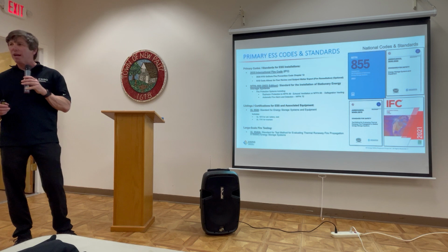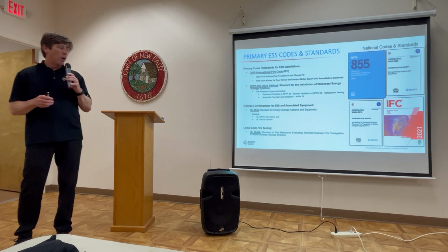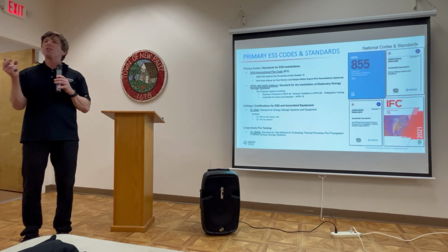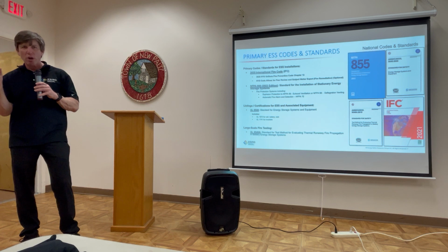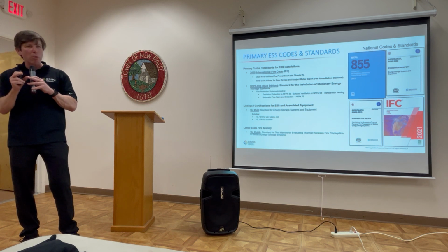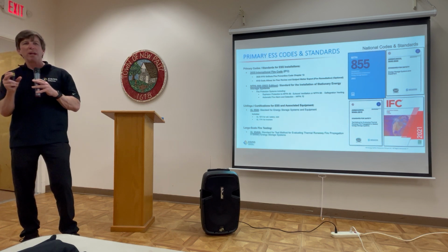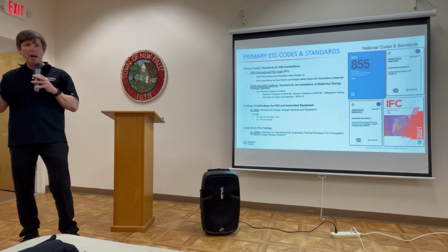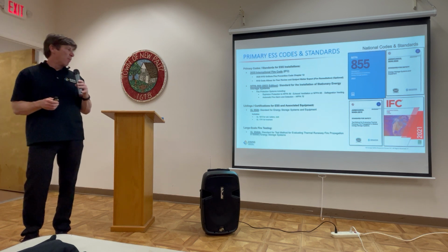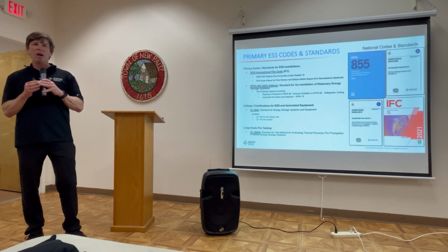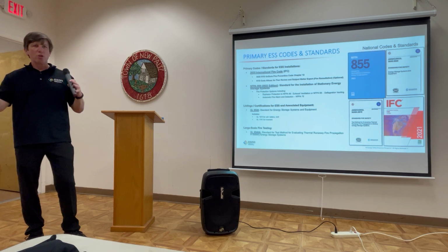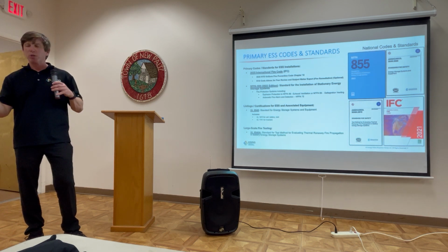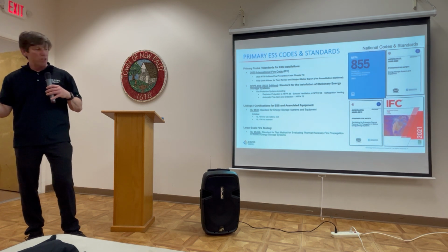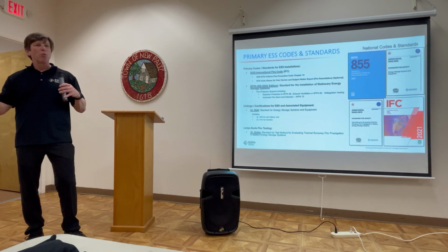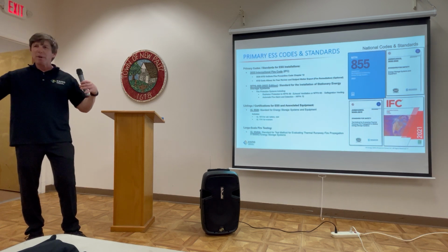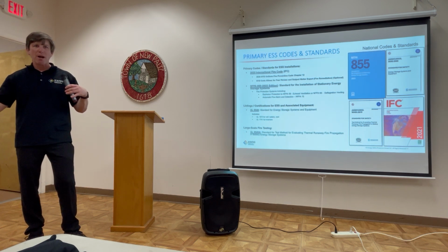That's something our company actually does. We have a laboratory where we force the individual cells I was talking about into thermal runaway just to see how it reacts, how much gas it produces, what kind of gases it produces. Then we test it on the modular level, where we try to get the module to catch fire, which is very difficult to do with these modern systems. And we build up to where we try to get the entire BESS system to burn.